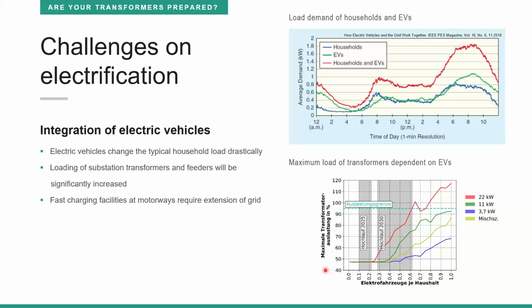We calculated how many electric vehicles are needed to bring the transformer to 100% of load. This is shown in the lower figure. So you can see the amount of electric vehicles per household, and the curves show, dependent on the loading power, the load on the transformers. And let's say if we have a three-phase loading, which is the green curve, and we have one electric vehicle per household, the transformers are loaded with 100%, which is of course the absolute limit.